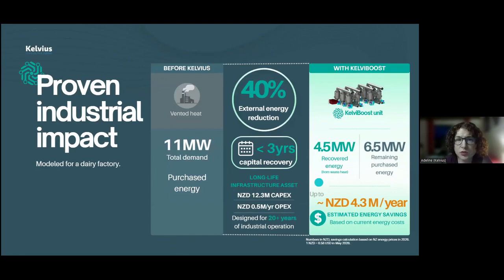When we take the performances proven at test rig scale, we can run feasibility studies and IRR calculations. For this specific real site, they require 11 megawatts total heat demand at the inlet of the spray dryer. We could abate between 2.5 and 4.5 megawatts of heat recovered and upgraded. It would require about 12.3 million New Zealand dollars in capex, plus some opex for electricity consumption of our auxiliaries. We've proven we can achieve an IRR between 28 and 45%.